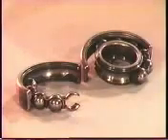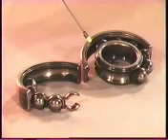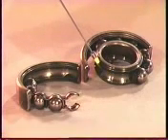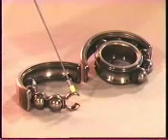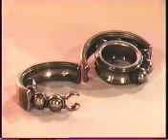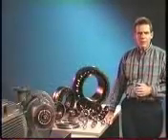These defect frequencies can be calculated individually for the outer race, the inner race, the cage or fundamental train, and the balls or rollers. Let's take a look at how these can be approximated using an actual bearing on a shaft. The defect frequencies are often expressed as a multiple of the turning speed of the shaft. That is, for each revolution of the shaft, how many impacts will be made due to a particular fault.